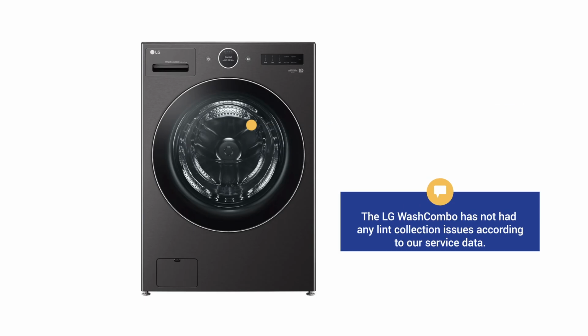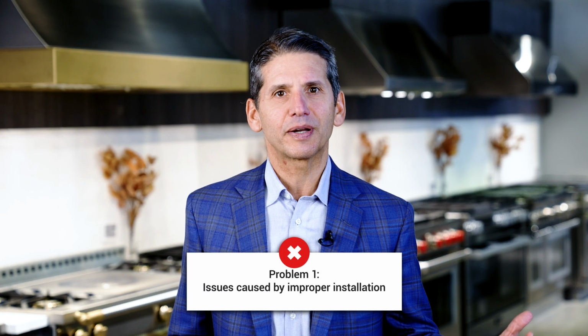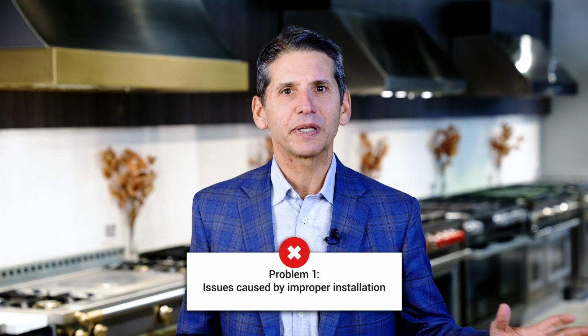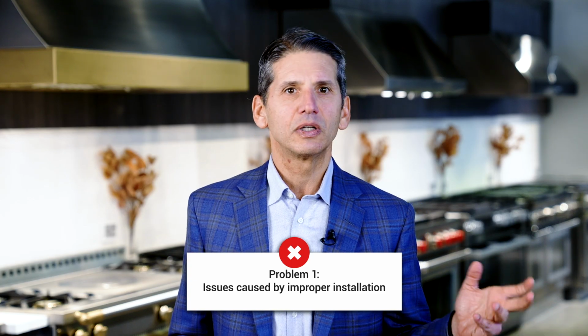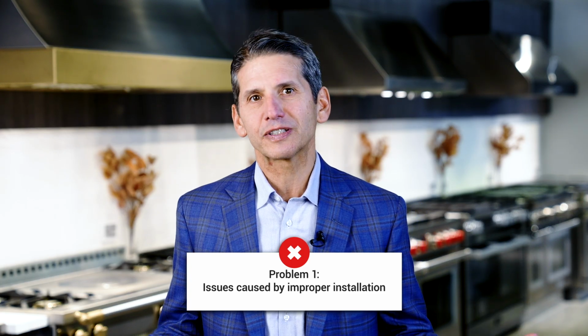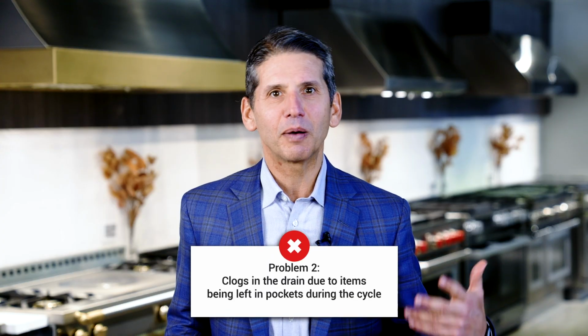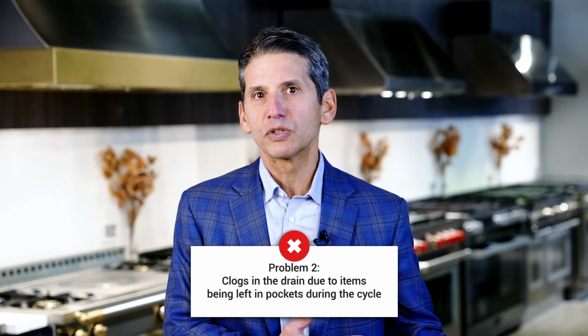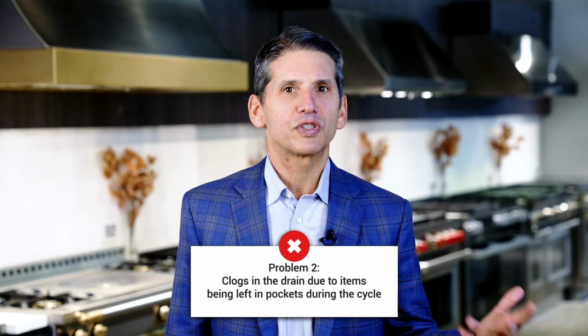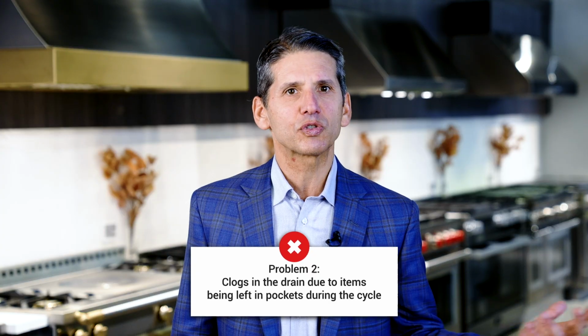Problems are relatively minor. The most common ones are drainage setup issues caused by the drain hose not being positioned at the right height during installation, which affected venting. But the main preventable problem is drain pump obstructions, or something getting in the drain pump, which seems to be consistent with the next one as well.